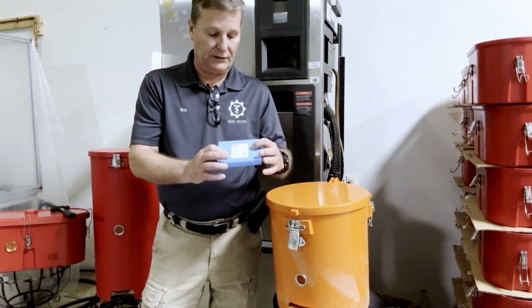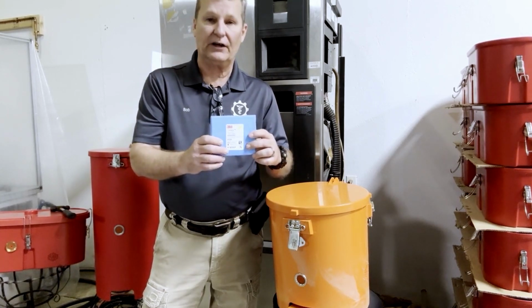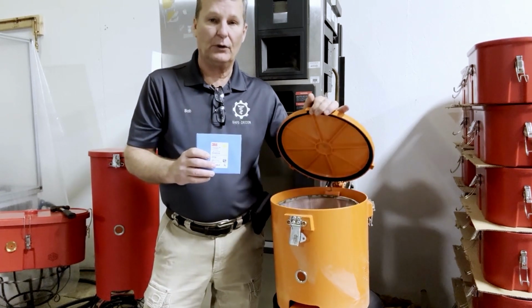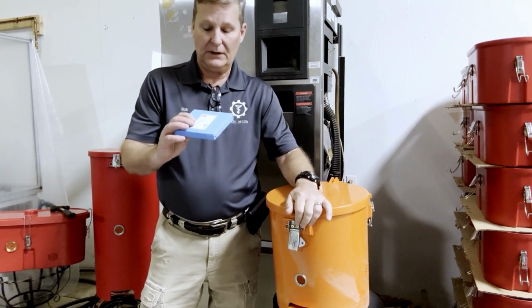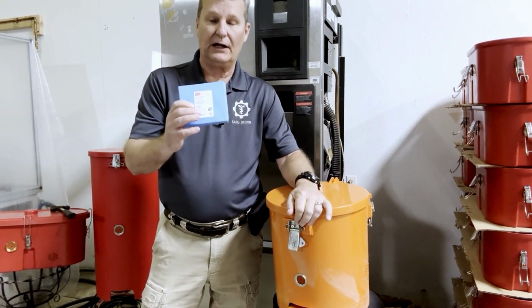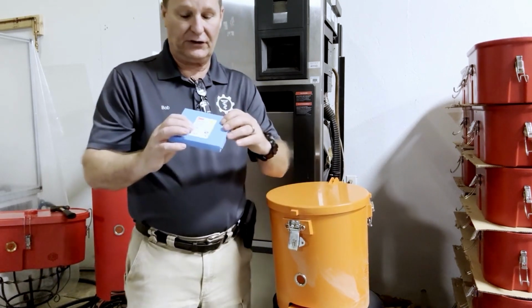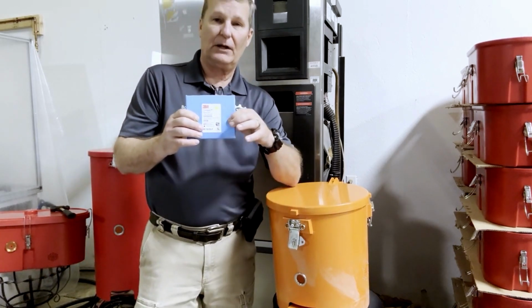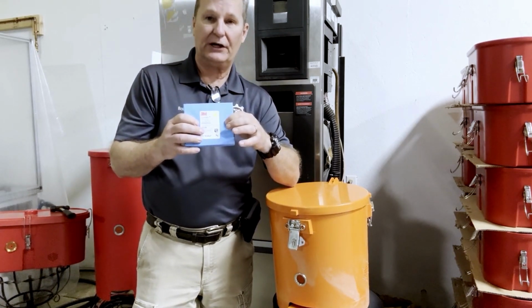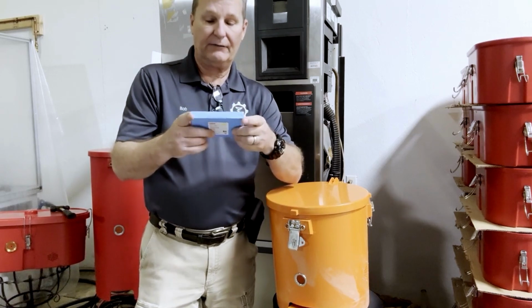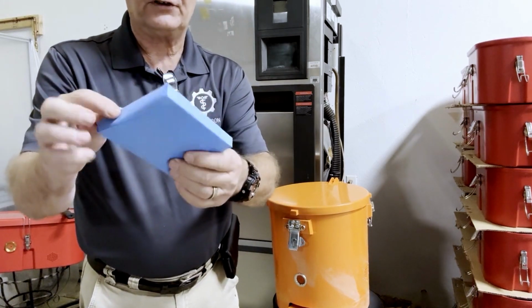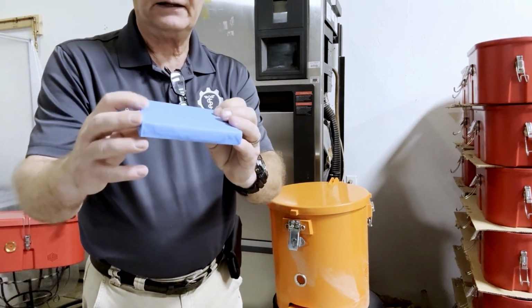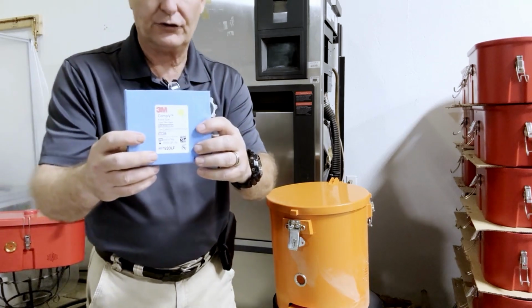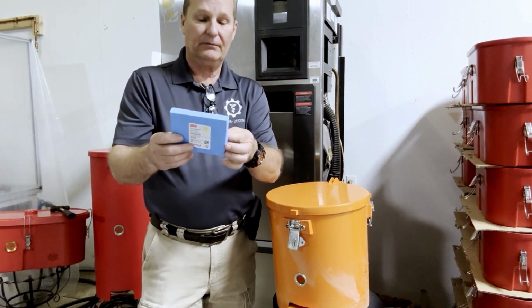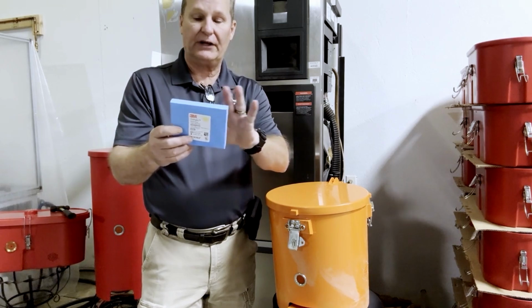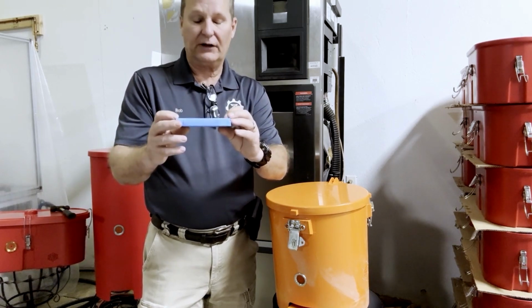Today we're going to run a Bowie-Dick or dart test in our BioPro 600 series. For those that do not know what a Bowie-Dick or dart test is, this is a steam heat penetration pack. You have the outer layer, which is folded up and sealed. This is the same material that they use for surgery. It's designed to allow steam and heat to penetrate, but it's thin-skinned.